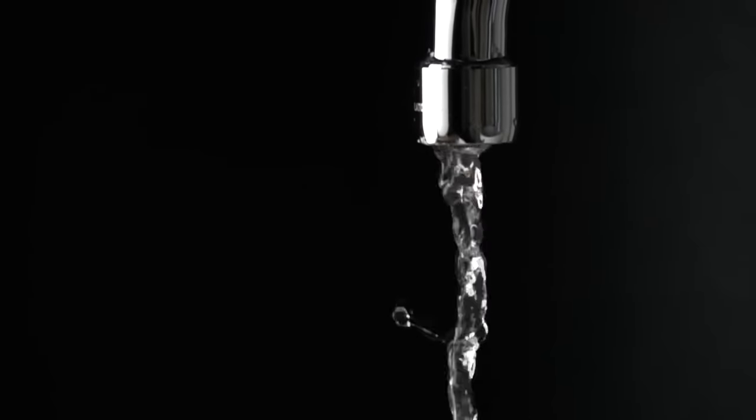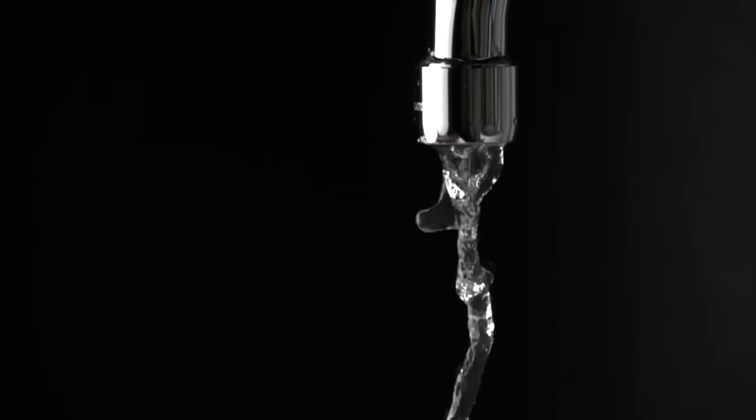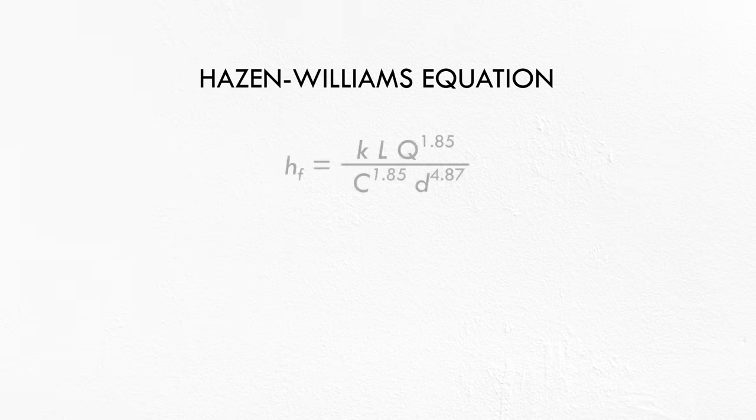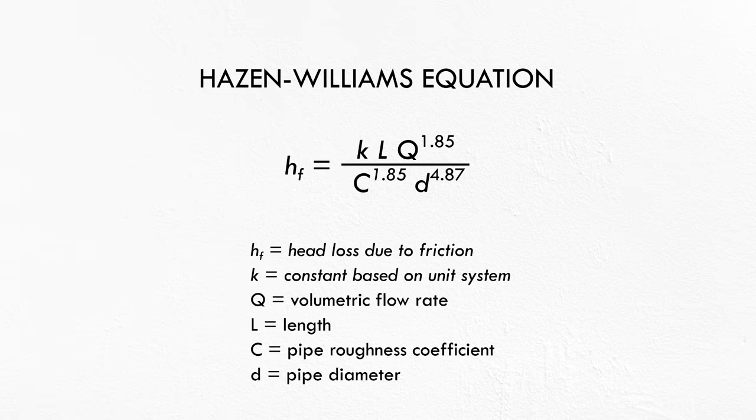There are a few methods engineers use to estimate the energy losses in pipes carrying water, but one of the simplest is the Hazen-Williams equation. It can be rearranged in a few ways, but this way is nice because it has the variables we can measure. It says the head loss, in other words the drop in pressure from one end of a pipe to the other, is a function of the flow rate and the diameter, length, and roughness of the pipe. Now, that's a lot of variables, so let's try an example to see how this works.